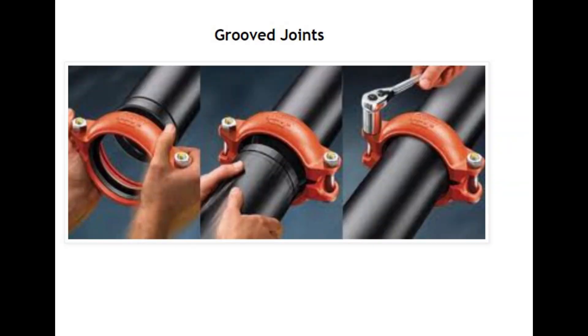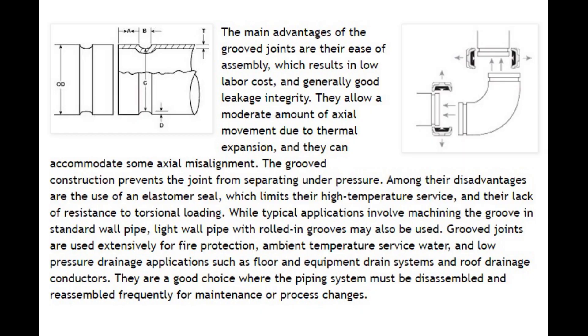Number 5: Grooved Joints. The main advantages of grooved joints are their ease of assembly, which results in low labor cost, and generally good leakage integrity. They allow a moderate amount of axial movement due to thermal expansion, and they can accommodate some axial misalignment. The grooved construction prevents the joint from separating under pressure.